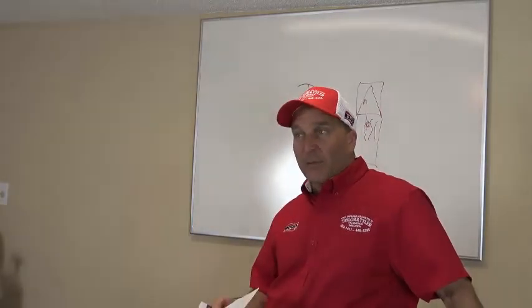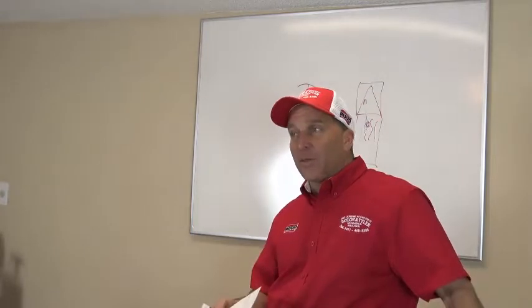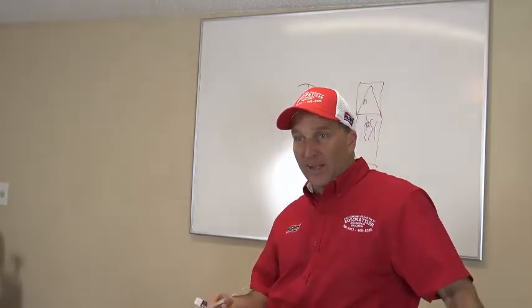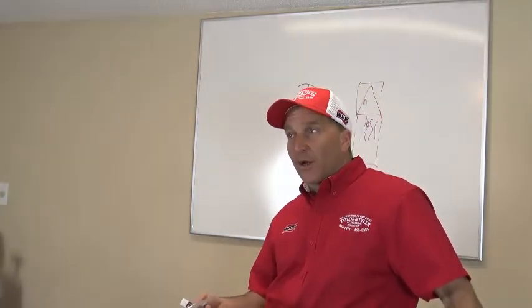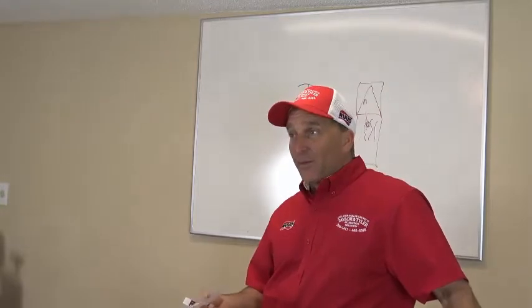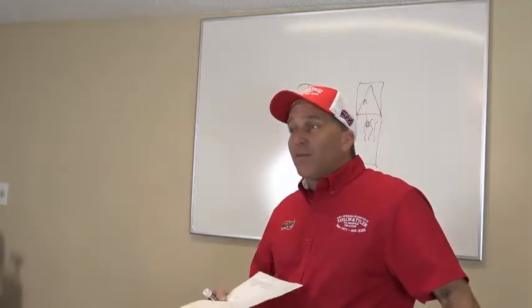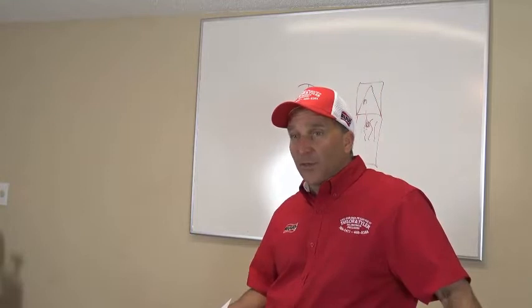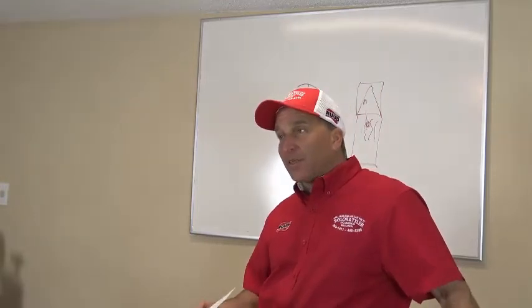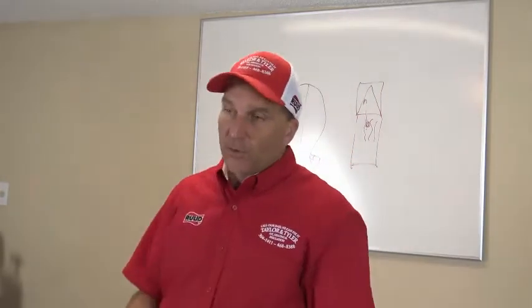Would you like to maybe look at that? Because how many times have you had to put refrigerant in your system over the last 3 years? Well, about every year I got to put refrigerant in. Well, I don't know who's been doing it. We may have even been putting refrigerant in for the last 3 or 4 years. And the customer may be saying, no, just add refrigerant, just put refrigerant, just put refrigerant.